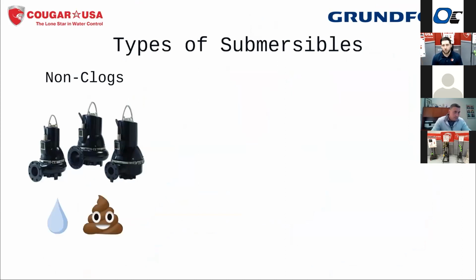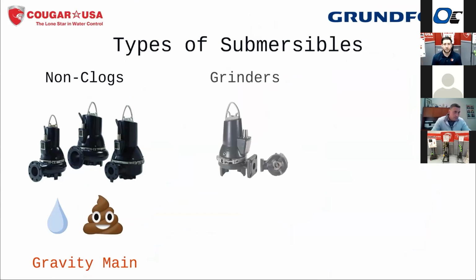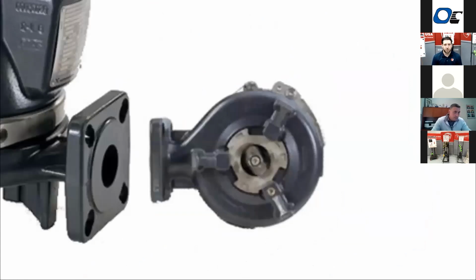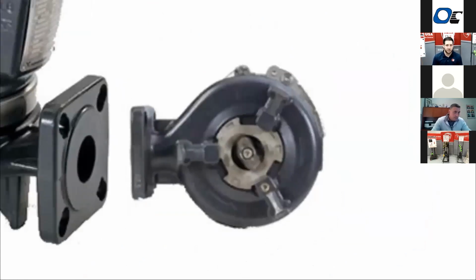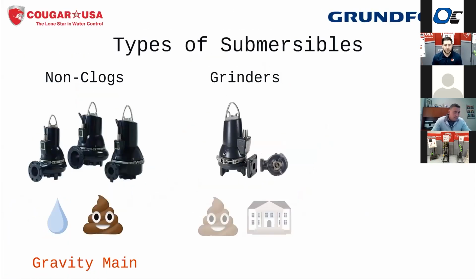But that's going to be good for storm or sanitary when we're pumping into the gravity main. Okay. We move to the grinder. You can see this has the much smaller inlet and outlet there. And we've got our two wheels there, the stationary wheel and the moving cutting wheel. It's a very small inlet and typically a 1.25 to 2 inch discharge. So it's got to chop up everything in there and get it out and be pumping against that high head. So again, force main applications for sanitary applications.